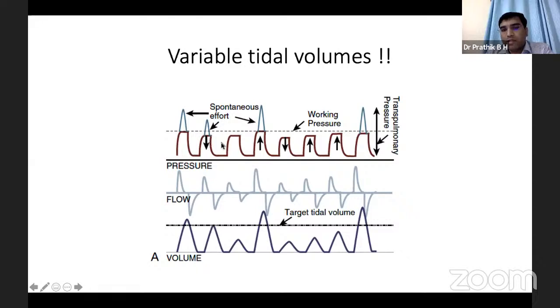In the third breath, the ventilator gives the PIP of the previous breath, because the ventilator assumes that the patient got an adequate tidal volume in the previous breath. But here the patient has not taken any spontaneous effort, so there is a drastic fall in the tidal volume. Since the tidal volume is reduced, the ventilator increases the peak inspiratory pressure. But here the baby has taken a spontaneous breath, so there is an overshoot of tidal volume. Again, since there is overshoot, the ventilator gradually adjusts the peak inspiratory pressure to achieve the targeted tidal volume. So if the patient takes a spontaneous effort, there will be an overshoot of tidal volume.